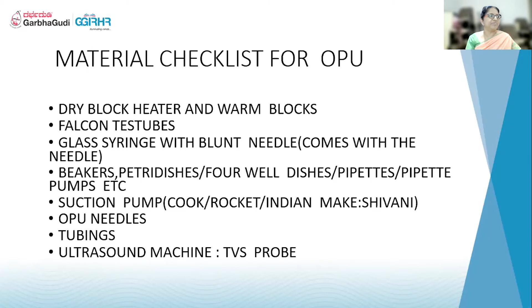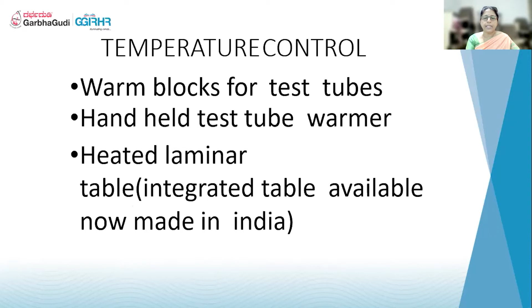So you should have proper temperature control, warm blocks for test tubes. OT technicians should come early and switch on the blockers because it takes time for it to reach 37 degrees centigrade. And you should have handheld test tube warmers also, and heated laminar tables where there are integrated tables of laminar flow with good 37-degree temperature maintaining tables. You have to invest in all this if you want to get a good success rate. So these are the warm blockers with test tubes inside maintained at 37. Immediately coming and switching on, it will not come to 37.